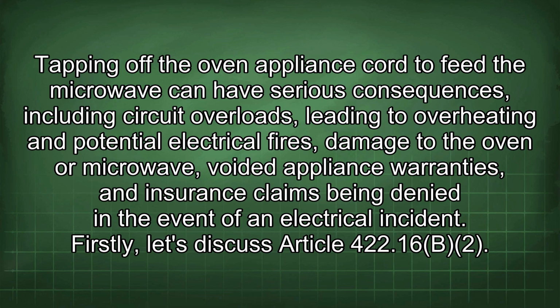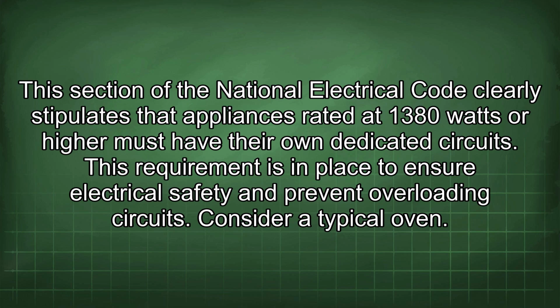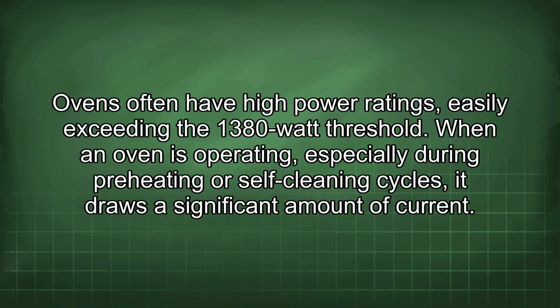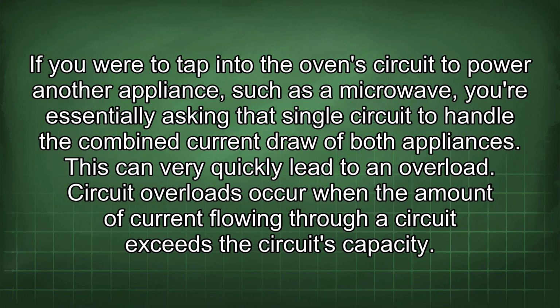Firstly, let's discuss Article 422.16b2. This section of the National Electrical Code clearly stipulates that appliances rated at 1380 watts or higher must have their own dedicated circuits. This requirement is in place to ensure electrical safety and prevent overloading circuits. Consider a typical oven. Ovens often have high power ratings, easily exceeding the 1380 watt threshold. When an oven is operating, especially during preheating or self-cleaning cycles, it draws a significant amount of current. If you were to tap into the oven's circuit to power another appliance, such as a microwave, you're essentially asking that single circuit to handle the combined current draw of both appliances. This can very quickly lead to an overload.